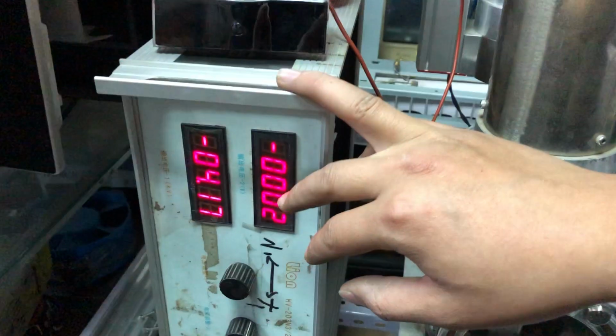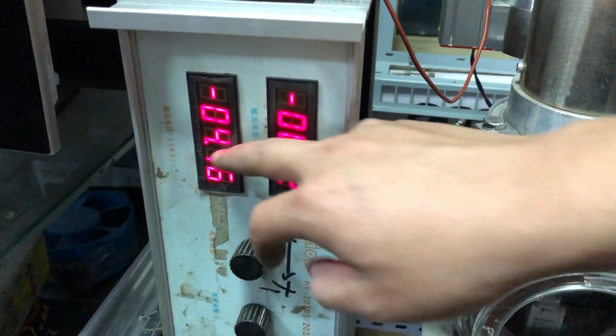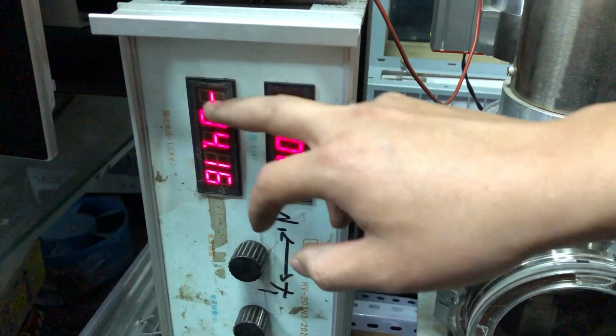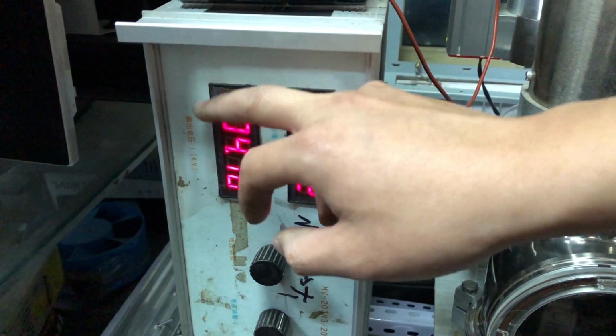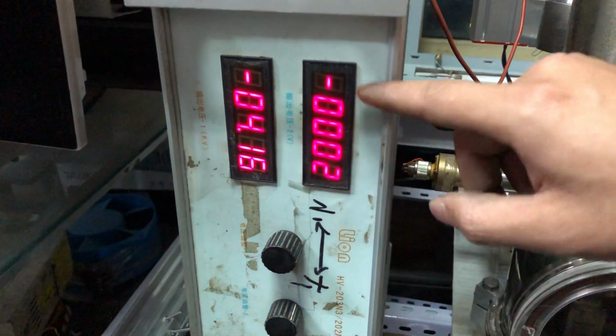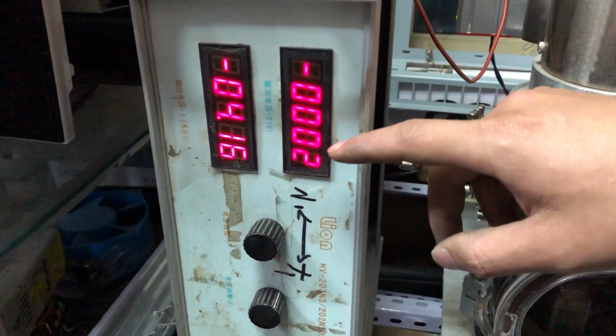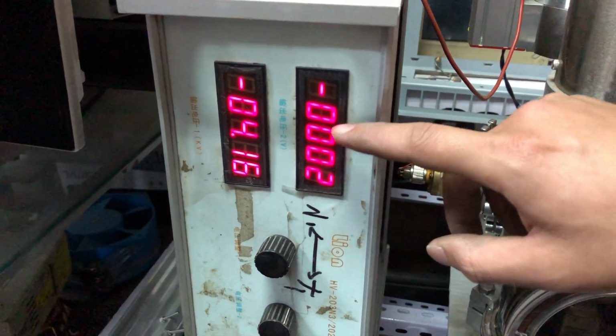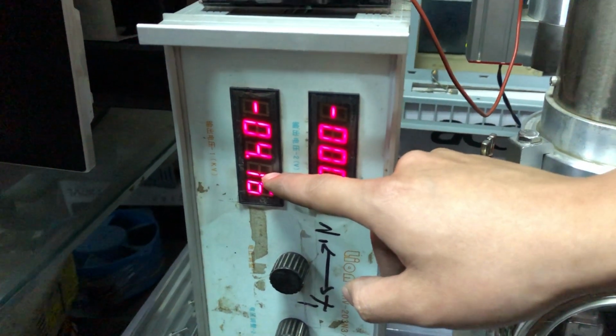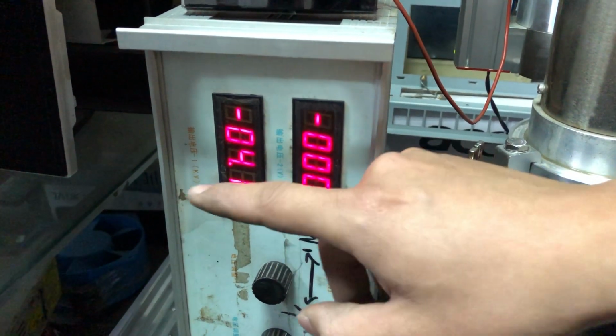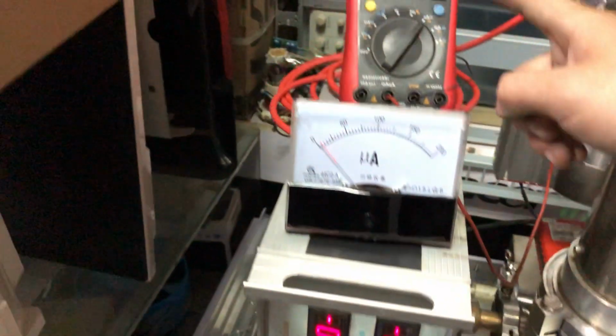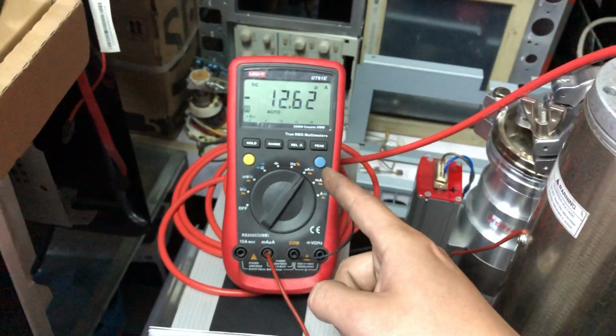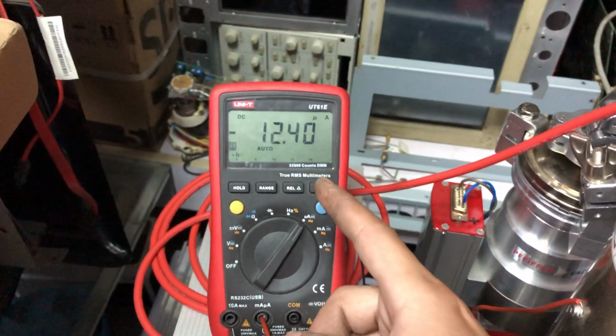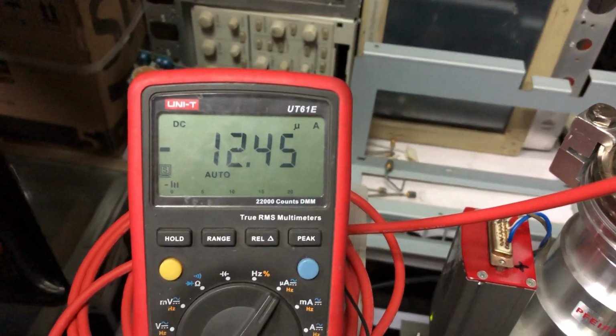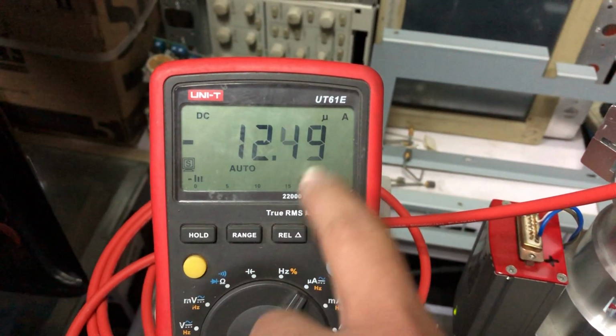So here is a high voltage power supply. It gives us two outputs. One is minus 20 kilovolts. The other one is minus 2 kilovolts. I'm going to use this as a focus voltage. This is the main emission voltage, or the acceleration voltage, and up here is a meter that's showing us the emission current. Okay, now about 12 microamps.